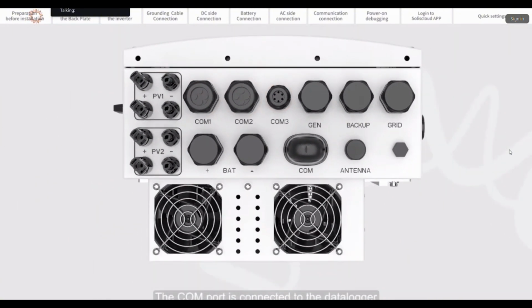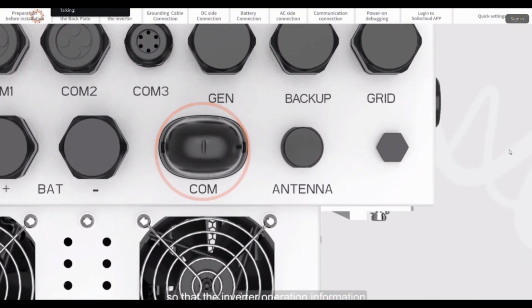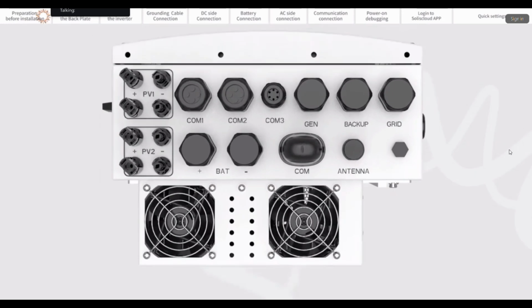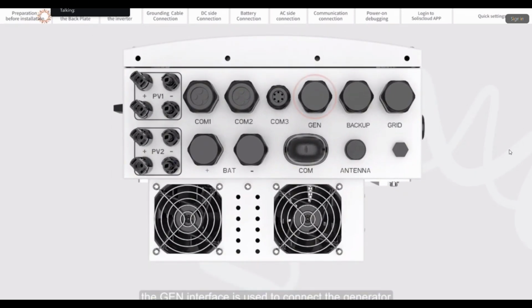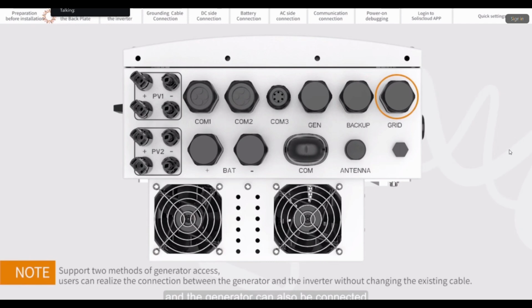The COM port is to connect the data logger, so that the inverter operational information can be uploaded to the Solis Cloud platform. Antenna is connected to the antenna to enhance the Bluetooth signal. The gen interface is used to connect to the generator. The load is used to connect to the backup load. The grid is used to connect to the grid, and the generator can also be connected to the grid port through the automatic transfer switch.